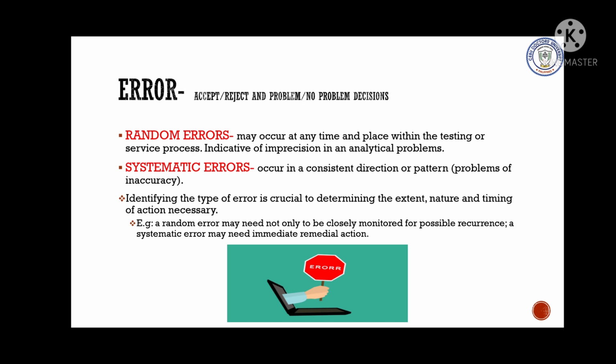Control charts and the multi-rule analysis may both give clues to the type of error because they show the violations of what type of rules again? The Westgard Rules. So when we say Westgard Rules, 1-3S and R4S are types of random errors, while 2-2S, 4-1S, or 10x or 8x rules that are being violated may indicate that the error is systematic.